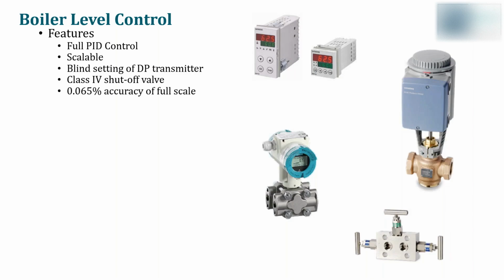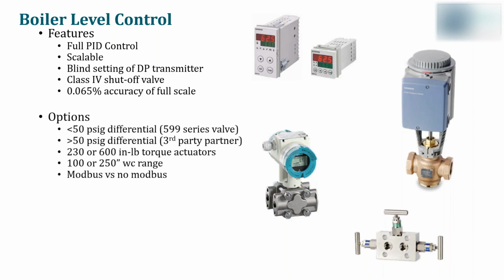Now, for the boiler level control, some of the features include it is a full PID control. It is scalable. The DP transducer offers you the ability for blind setting. What this means is you do not have to empty and fill the boiler to set up your DP transducer. It can be done based on measuring the height of the reference leg. It is a class 4 shutoff valve, and it does offer 0.065% accuracy of full scale.